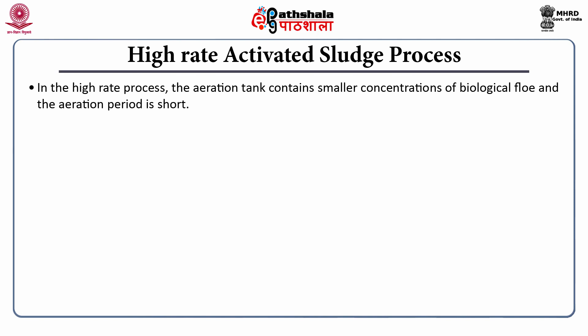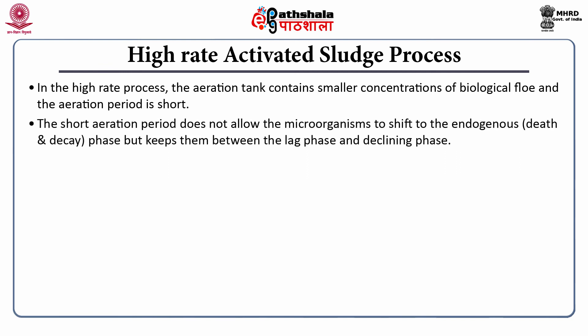Another modification is the high rate activated sludge process. In this process, the aeration tank contains smaller concentrations of biological solids and the aeration period is short. The short aeration period does not allow the microorganisms to shift to the endogenous phase but keeps them between the lag phase and declining phase.